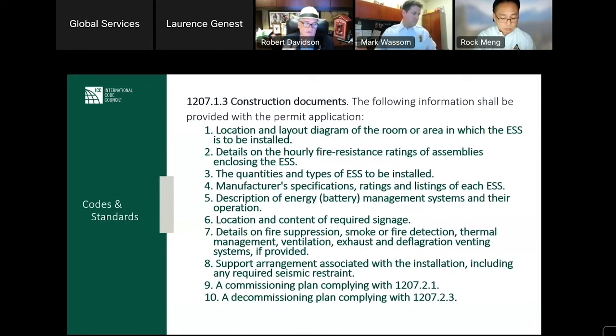So one of the key items of both NFPA 855, the International Fire Code, and NFPA 1, which now uses extracts of that, and other documents I've seen globally, is the construction documents, the amount of information that needs to be submitted up front. In the construction world, we like to do a lot of deferred submittals. But when it comes to energy storage systems, so many of the components relate to each other. The HMA, hazardous mitigation analysis, for example, looks at the whole installation. Well, you need all this documentation up front to do a thorough review to see if all the pieces match, so that at the end you're going to get a reasonably safe installation level. Next slide, please.